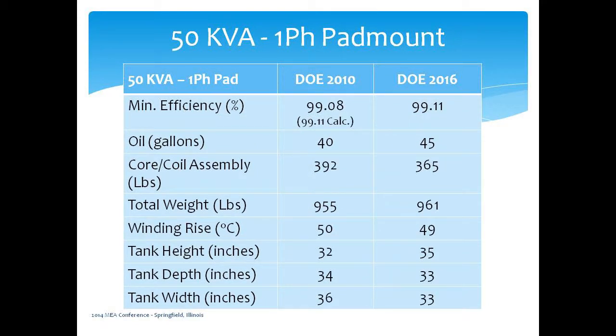And I flipped over to the 50 kVA pad-mount because some of these are very, very unusual. When you look at the winding rise on this one in particular, you can see that we're nowhere near a 65 degrees C winding rise. With the amount of oil in it and the size of the core coil assembly, it just runs really cool. And of course, when the 2016 requirements impact it, what's going to happen? It's going to run even cooler, with a little bit more oil in the size of it.